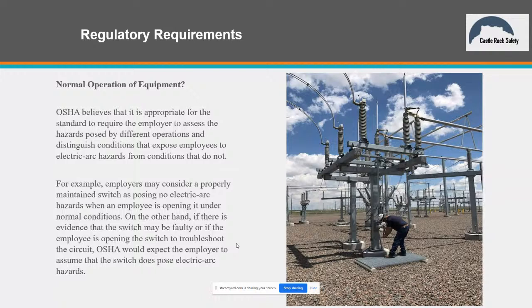So if this person is standing on that mat and opening this switch, and he's outside that 2-calorie boundary, he would not be required to wear arc flash clothing. Now, this is where it gets a little tricky with 1910.269. He may be outside that 2-calorie boundary, so he's not exposed to an arc flash. However, if there's a switch failure and there's all this vaporized and melted material that could shower down on him, it could ignite his clothing. So they say in that case he would need flame resistant clothing. This gets a little confusing because 1910.269 says sometimes a guy might need flame resistant clothing, but he doesn't need arc resistant clothing.